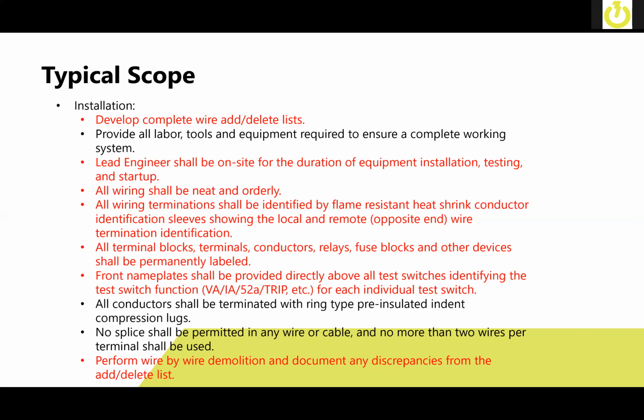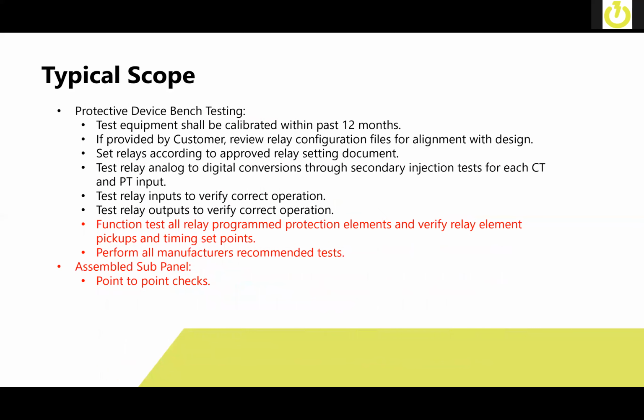Wire by wire demolition and documenting any discrepancies. This comes into play whenever we're trying to verify the design of the system before it gets fully installed, make any necessary changes while we're in the middle of the installation, versus at the end where we're trying to do startup and you may be starting up a generator or a motor or a transformer and the system doesn't operate properly or fails to operate.